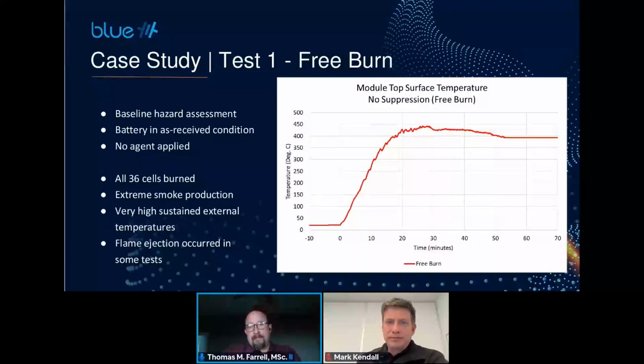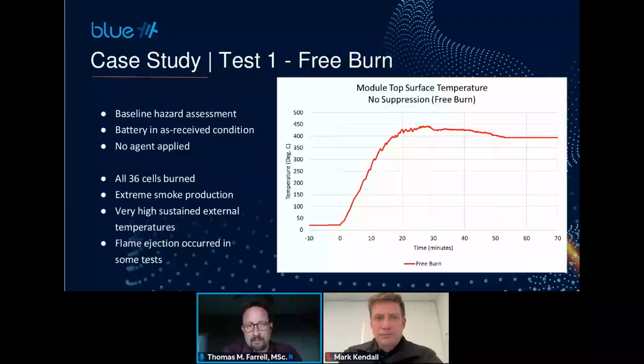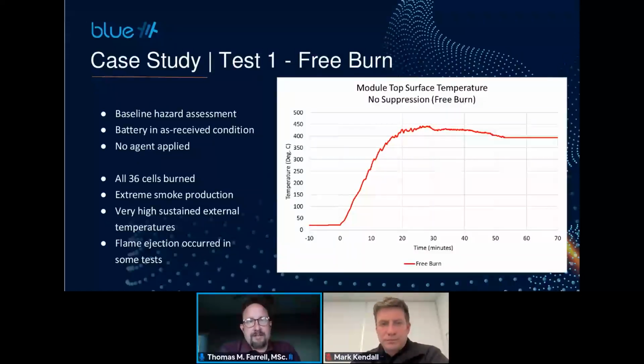So we tried that. Before we did any testing with blue, the very first thing, and this is our case study, with that same battery that we showed in the beginning, was a free burn. Let's just see how bad things get. We measured a lot of things on this test, and the one that tells a pretty good story is the temperature on the top of that module. We had a stick-on thermocouple right on that upper surface to see how hot things got.